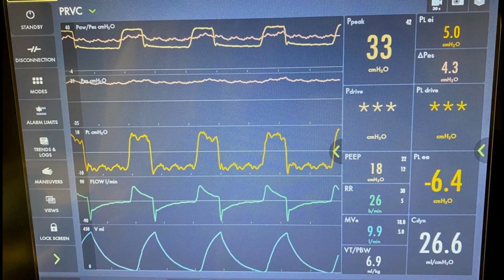Verify that cardiac oscillations are present on the esophageal pressure waveform. If not, then apply pressure to the patient's abdomen while observing the ventilator waveform. If a positive deflection is noted, then the balloon is likely within the stomach and should be withdrawn until strong cardiac oscillations are observed. Once present, proceed with the occlusion test.